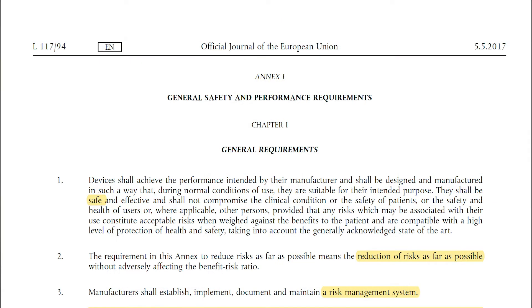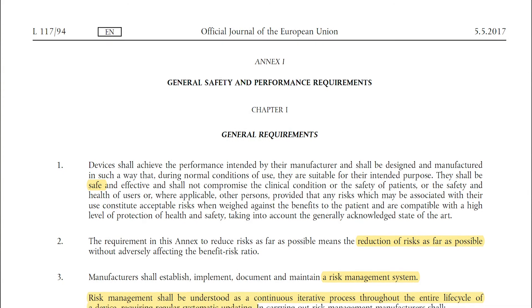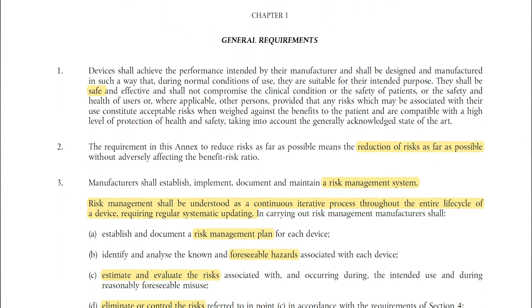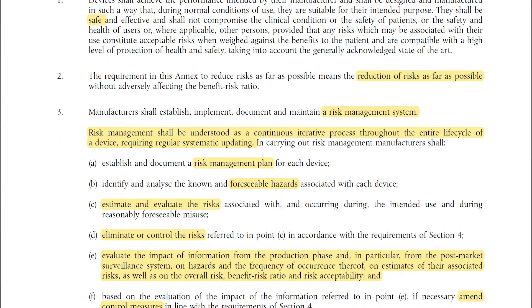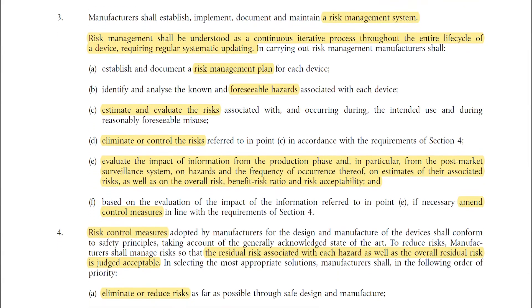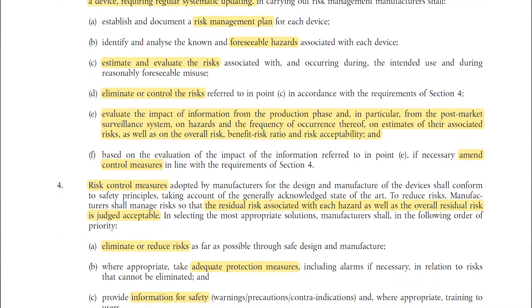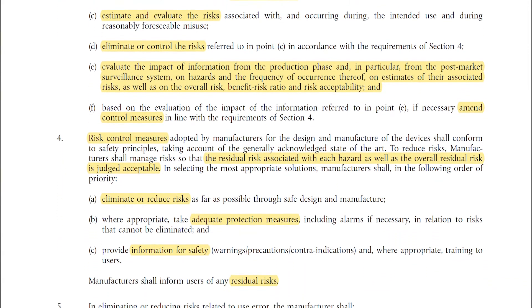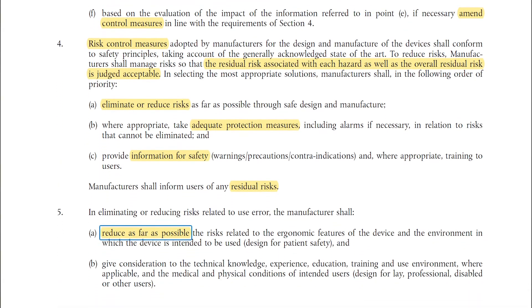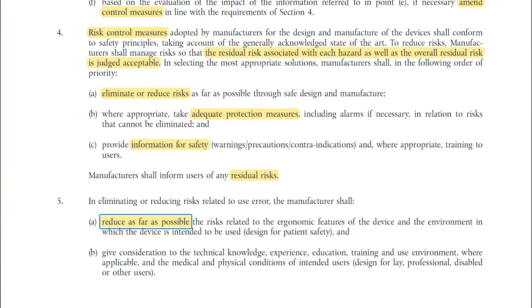In fact, risk management is mentioned quite a few times in the medical device regulation, or MDR for short. Just like ISO 14971, the MDR requires you to have a risk management system, and there are a lot of requirements on what your product should be like in regards to risk and safety. These product-specific requirements are found in Annex 1 of the MDR — the general safety and performance requirements. Let's look at an example of what you have to do in the risk management process from start to end.